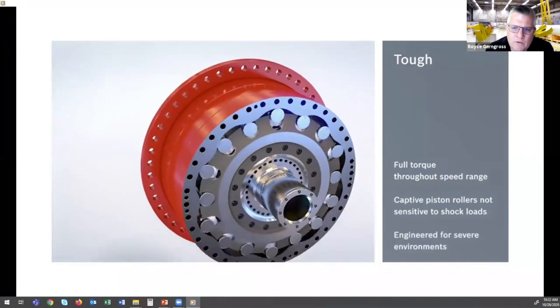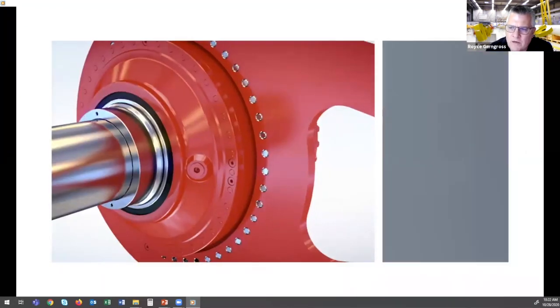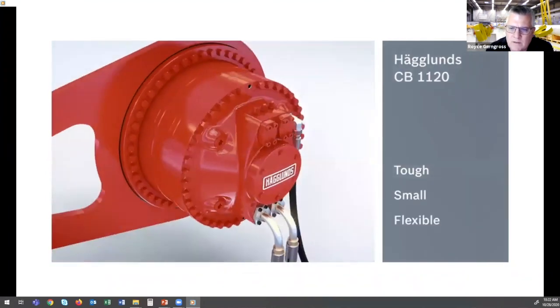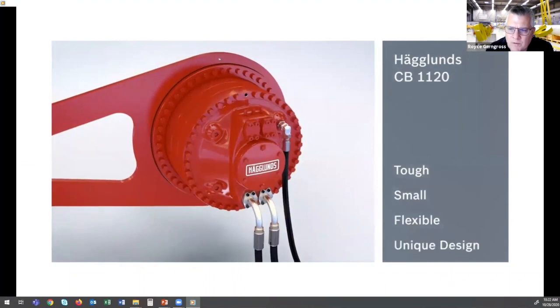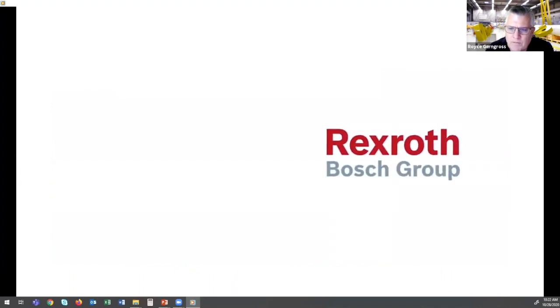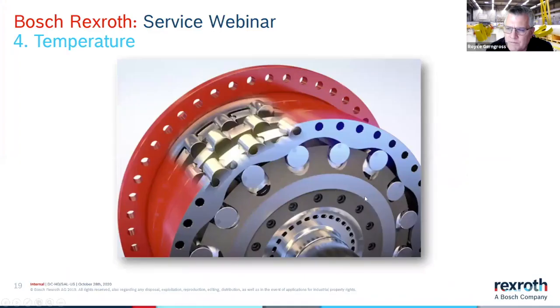If the oil is too thin or not viscous enough, the surfaces will contact and grind, creating heat, raising oil temperature, which lowers the viscosity. This is a runaway problem, as more heat creates less viscosity, and that creates more heat, and so on. If the oil is too thick, it doesn't flow, causing problems like cavitation or, at a minimum, very low efficiencies in the system, thus hurting the power transmission function of the entire hydraulic system.